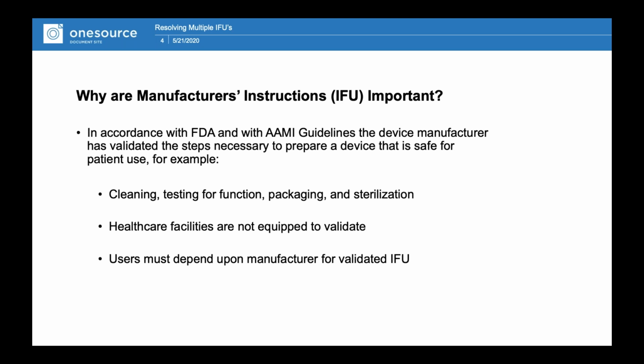I put that in there because these terms are used loosely very often. Validation is what occurs during the 510K process. We covered that. We spoke about that. The manufacturers are doing that either internally or they're doing it with an independent test lab. I can't exactly say that facilities are not entirely, they're not typically equipped to validate. What we do is we get medical devices into our facilities. We're looking at validated IFUs from a manufacturer that were cleared, and then we're trying to verify that. We do verification. We're trying to mimic to the closest of our ability the cleaning and then the biological testing and chemical indicator testing that's happening over on sterilization.